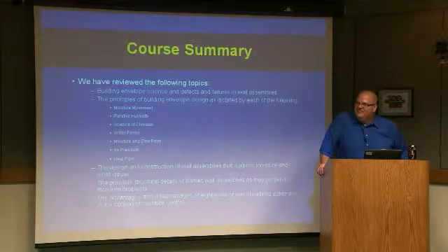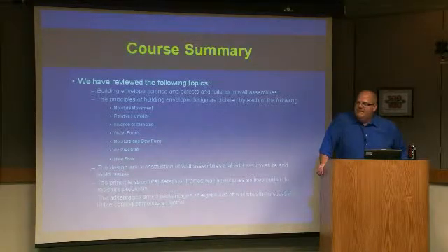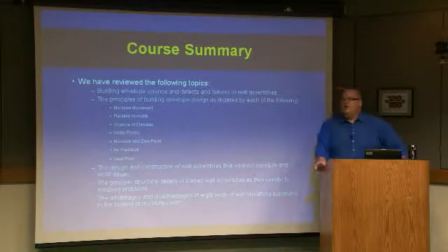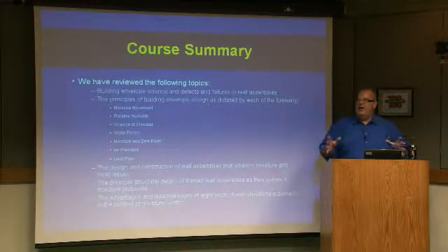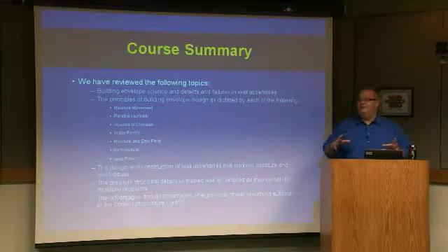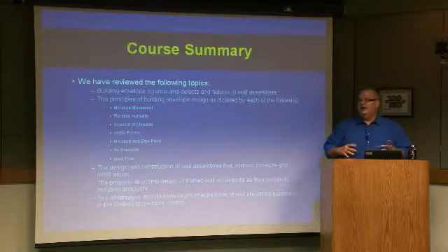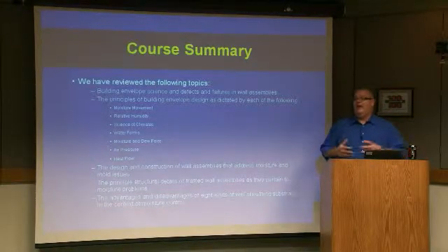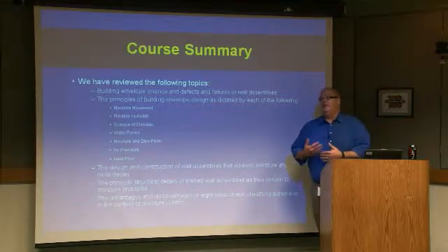Thanks for that. You said if you take a volume of air and decrease the temperature, the humidity level goes up. Now I'm thinking there's more moisture in warmer air. Right. So if we took that volume of air, and it had a fixed set of moisture in it, when we decrease the temperature, it can now hold less, which causes the relative humidity to go up, because relative to how much it can hold at lower temperature, that would increase.